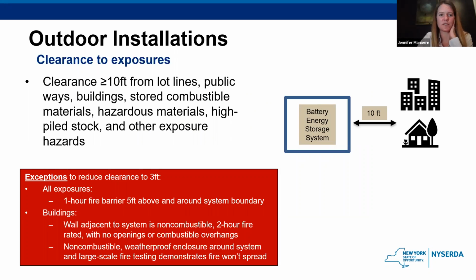Okay, so outdoor installation requirements, they need to have at least a 10-foot clearance from lot lines, public ways, buildings, etc. This is the same list we saw before, basically 10 feet from all of those different exposure types. In the red box, there are some exceptions to that. I don't know if we want to go through all of them, but just know that they are there. There are always some exceptions to be made in some of these. So for example, if the building that happens to be near the energy storage system is made of non-combustible materials, maybe you can get closer than 10 feet to that building, as an example.